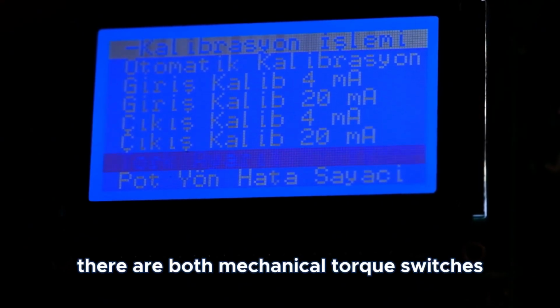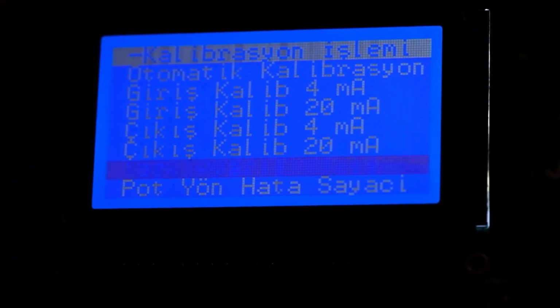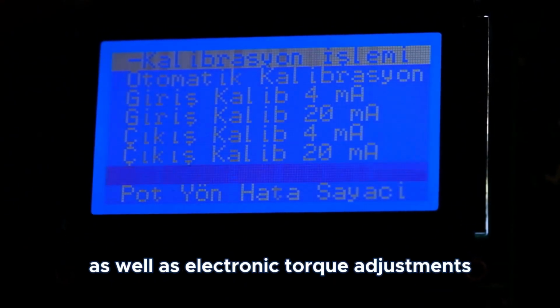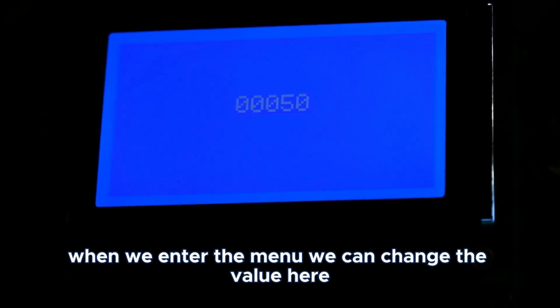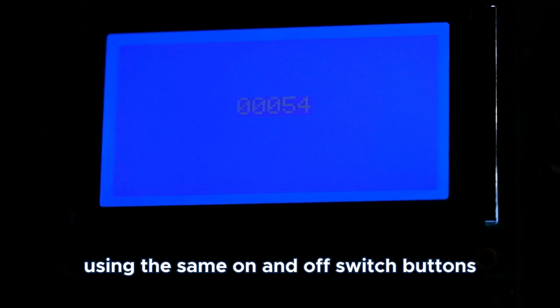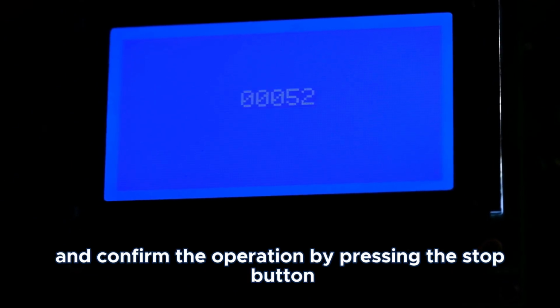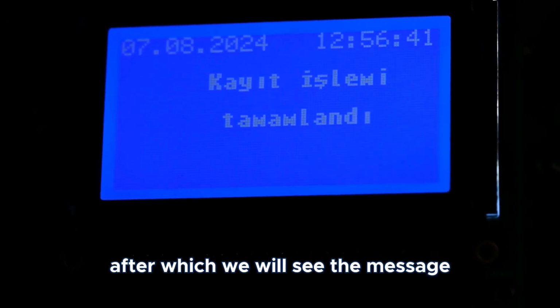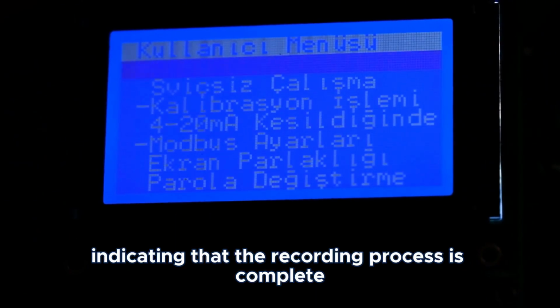In the torque setting, there are both mechanical torque switches in the Focus actuator, as well as electronic torque adjustments. When we enter the menu, we can change the value here using the same on and off switch buttons and confirm the operation by pressing the stop button, after which we will see the message indicating that the recording process is complete.